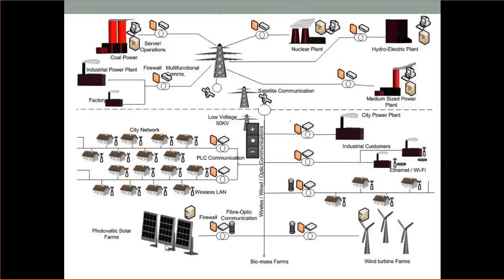Here's another problem that I didn't cover that I probably should have. Let's say the wind power's operating at night. Let's say I'm getting a lot of wind at night. Well, that's when my nuclear plant would be running at 1,000 megawatts. So now maybe I need to bring my power plant down from 1,000 to 950 megawatts because I got 50 megawatts of wind generation. Well, my nuke plant might not operate quite as efficiently at 950 megawatts as it did at 1,000. So I'm operating this unit a little more inefficiently to accommodate this power. And also now I'm not generating revenue at this, and I've got my bonds that I have to pay. And this was pretty expensive to put in. I got bonds to pay here too. But there's another constraint. There's another problem that I need to work on.